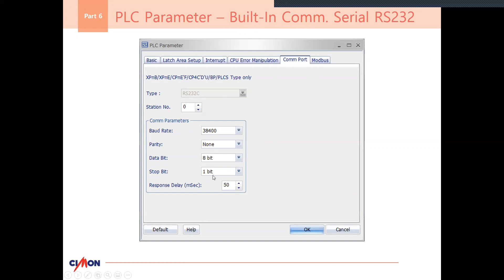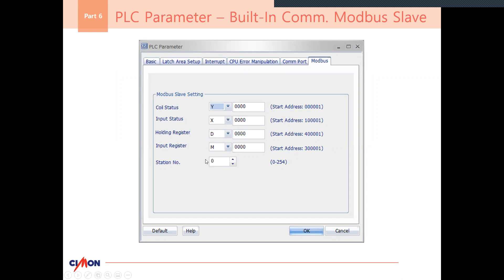If you're going to do Modbus master, that is part of the actual making a program. So if I right click on program, new program, you'll see I have master Modbus right here for serial, and then you'll see I have Modbus master for TCP right here. So this is where you do master for Modbus, and then slave is done in PLC parameter. So you're just setting up the device registers and then the station number accordingly.